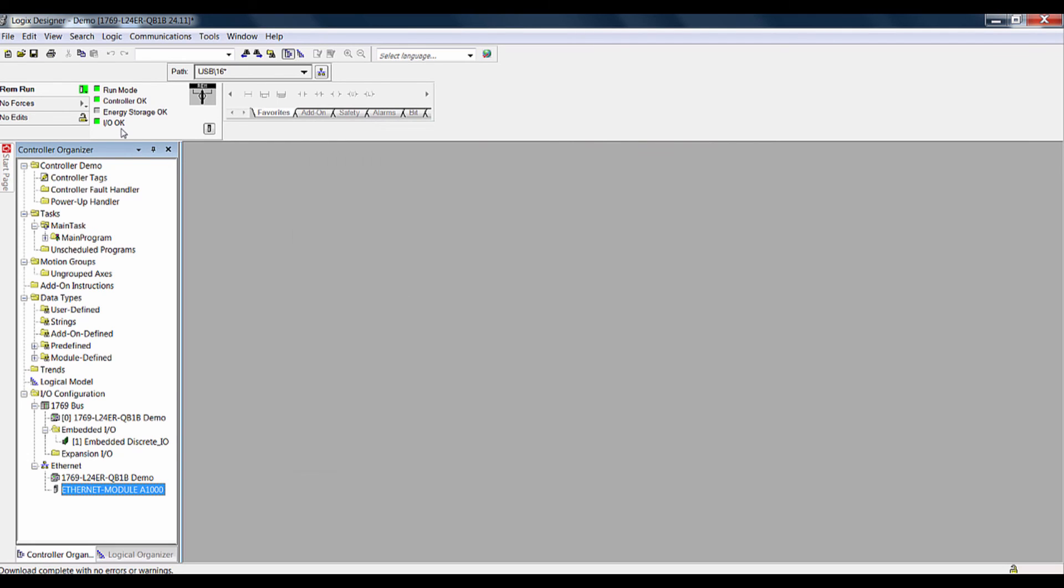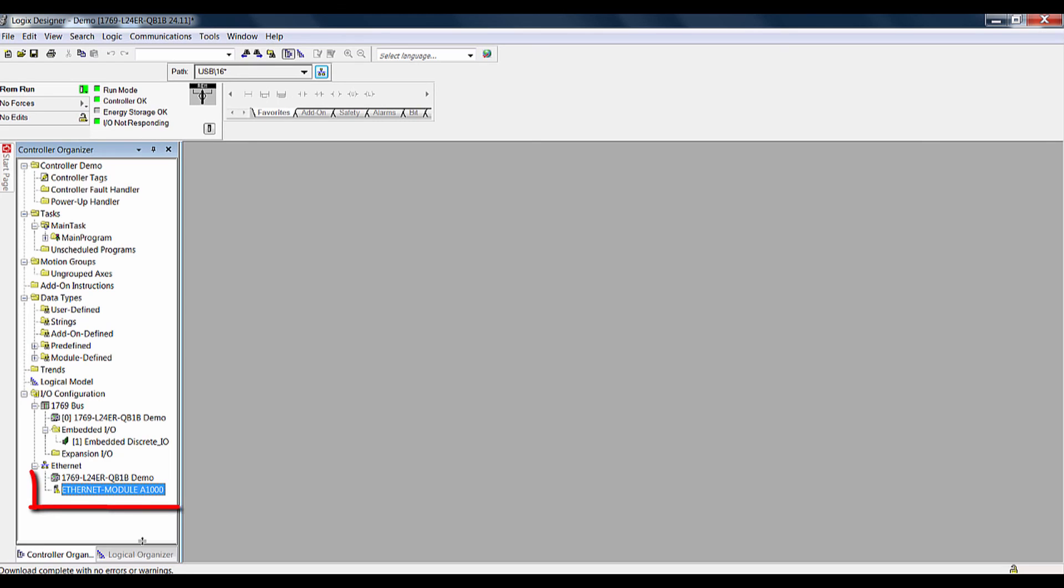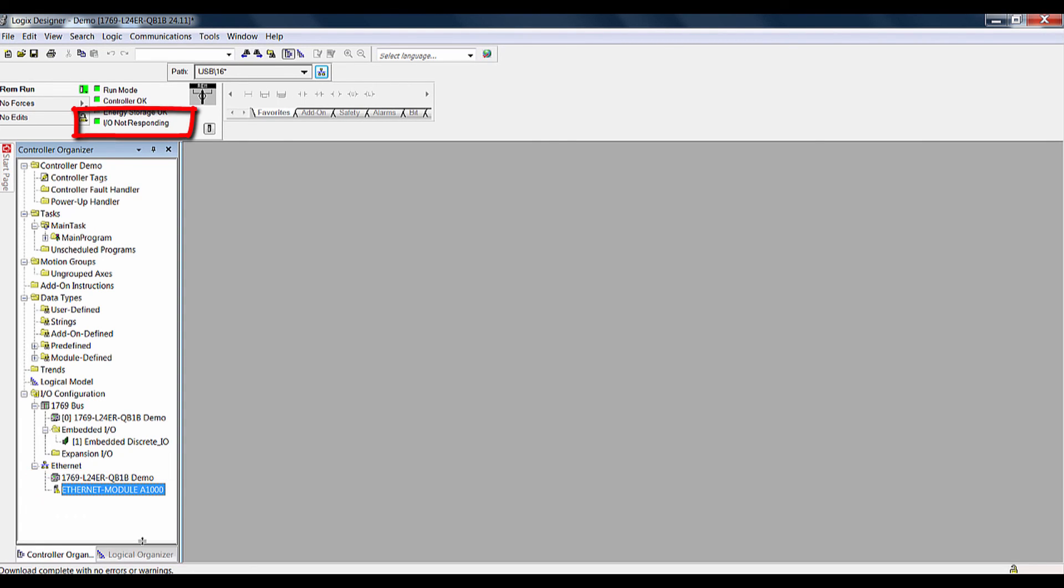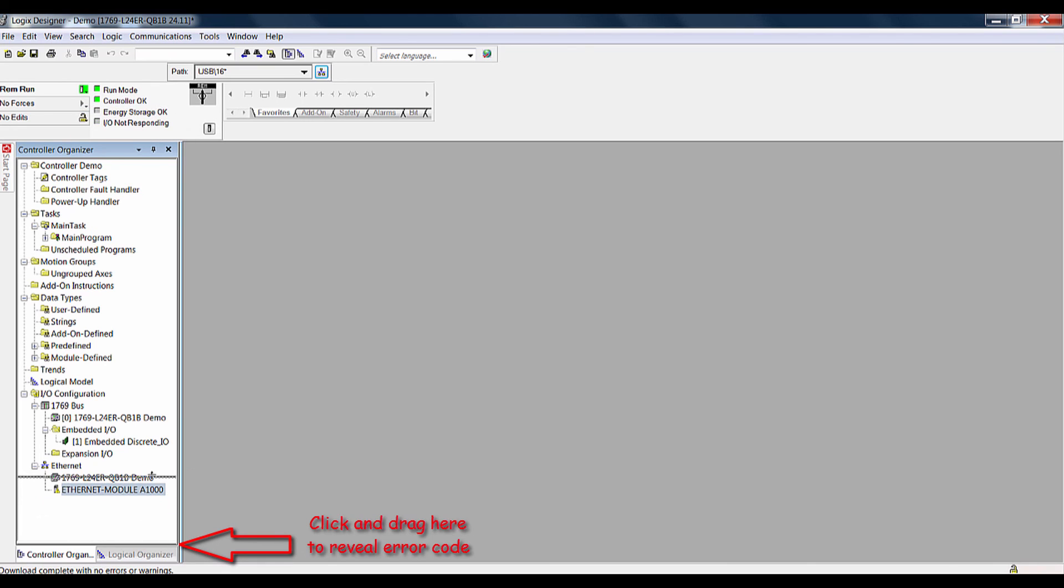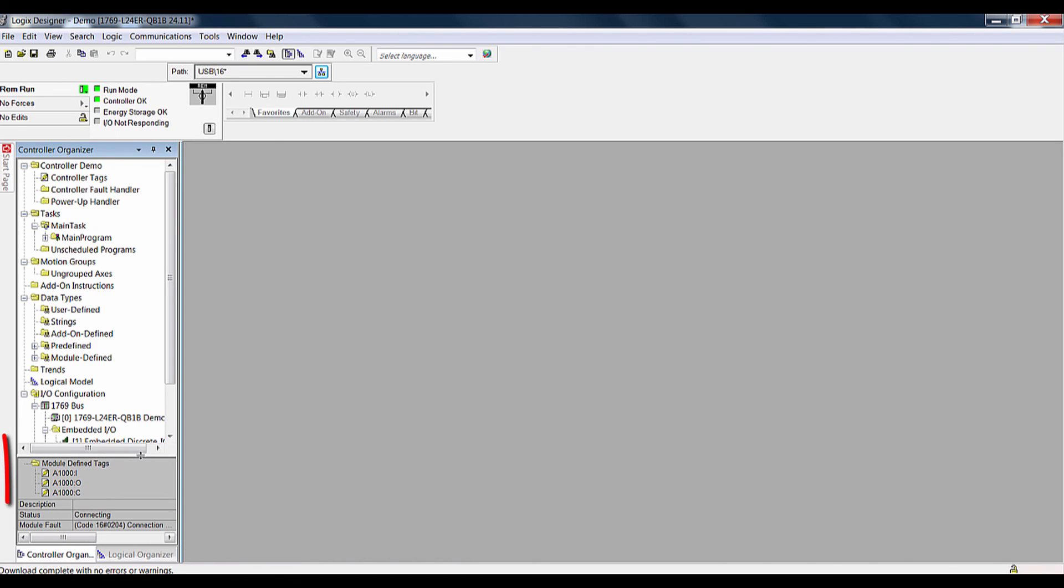If there are no configuration or communication errors between the PLC and VFD, the status will read IO OK. Otherwise, you will get a yellow triangle with an exclamation point in it next to the drive and the status will read IO NOT RESPONDING. Please refer to the error code generated to help troubleshoot this situation.